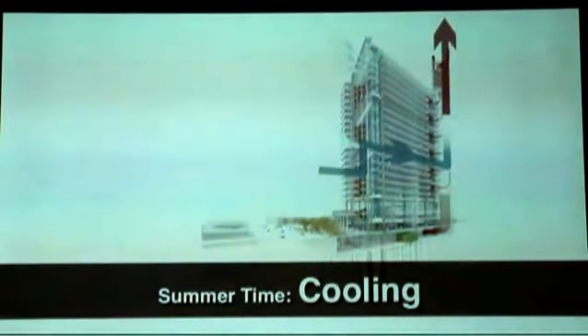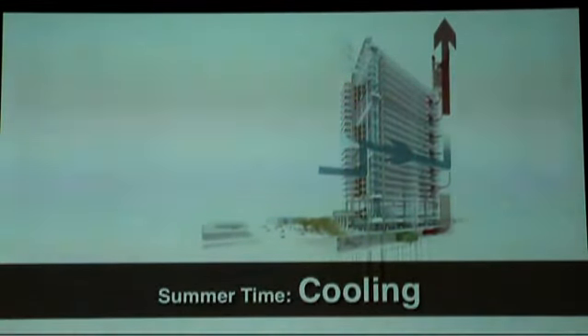In addition, we have about 300 geothermal boreholes under the building. You drill down about 120 meters, put in a closed loop water tube, pour concrete on top, and create a heat exchange with the ground. This heat exchange provides 100% of the cooling required for the building and about 50% of the heat.